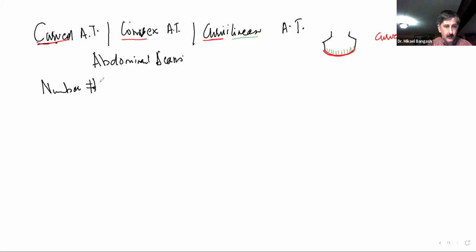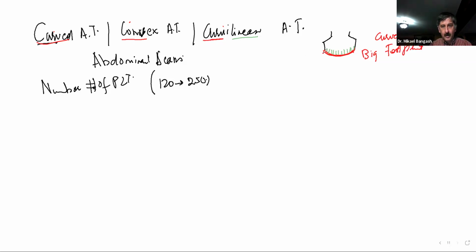How many crystals do we have here? The number is pretty much the same as that of a sequential or linear sequential array, so anything between 120 to 250. Now traditionally, when we look at these transducers, not only is it a curve, but it's also going to be a big footprint. If we measure all around, it's going to be approximately 10 centimeters in most cases.